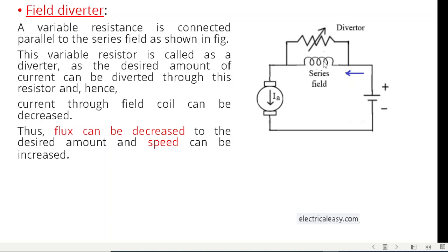Now we introduce the diverter — a resistor connected in parallel with the series field winding. When the diverter is added, the current divides into two paths, reducing the series field current. This reduces the flux, and therefore the speed increases, since speed is inversely related to flux.